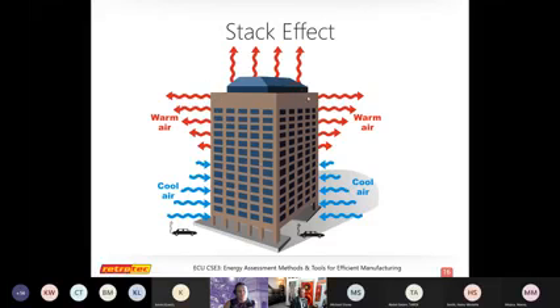And so if you're able to tighten that building up to reduce that stack effect, it's going to allow that HVAC system to satisfy the thermostat a lot easier and not have to work as hard. So along with the wind that creates leaks in buildings, and the fans that we already have running, the stack effect is always working against us too in the more extreme times of the year. So the taller the building is and the larger difference we have between indoors and outdoors as far as temperature goes, the stronger that stack effect is going to be. But we can mitigate that by sealing up the building as much as we can to stop that from happening.